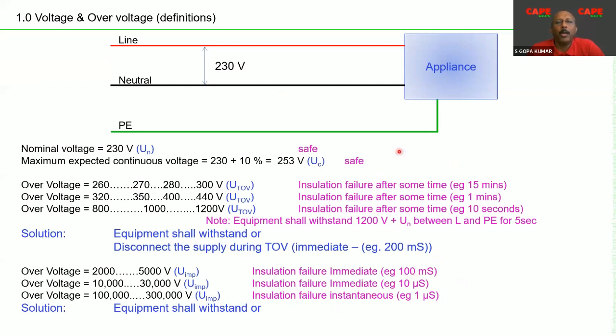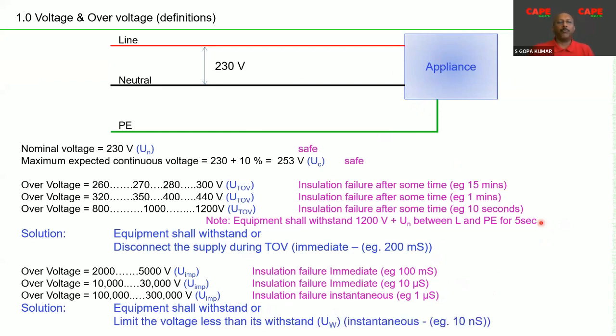The two ideas which can be implemented to protect the equipment are, first, equipment shall withstand. The equipment manufacturer decides that I make an equipment which is very, very strong against transients, so my equipment is able to withstand. I don't need anything extra. So this is one idea which can be implemented. And the second idea is, you limit the voltage to less than its withstand voltage.